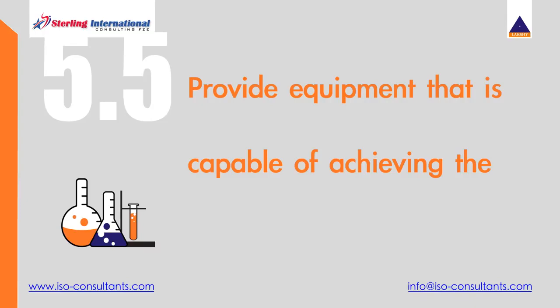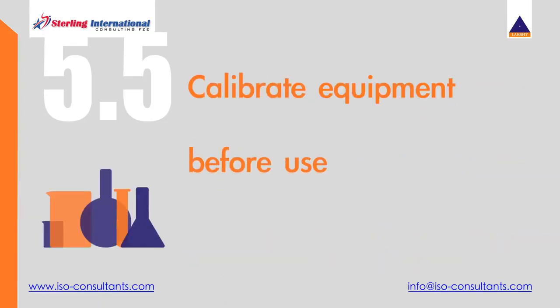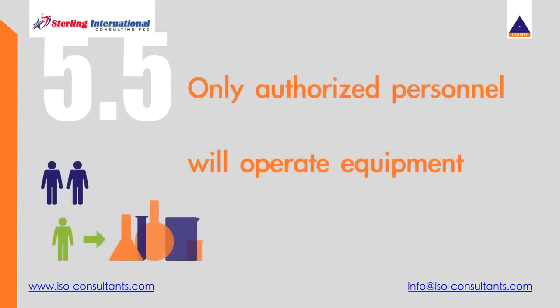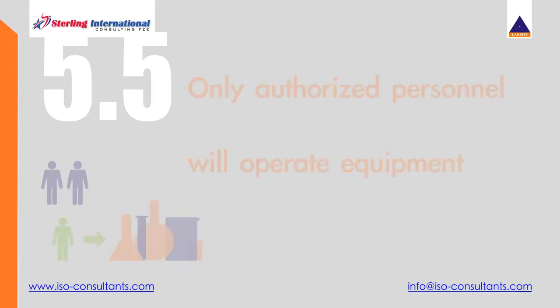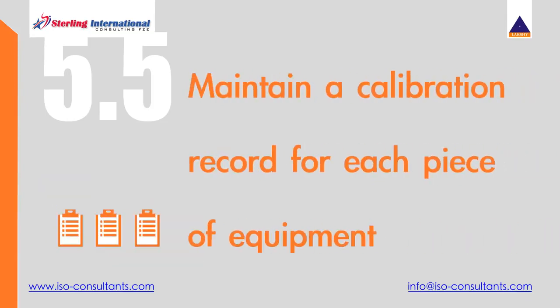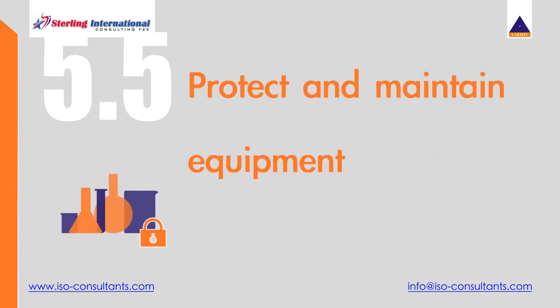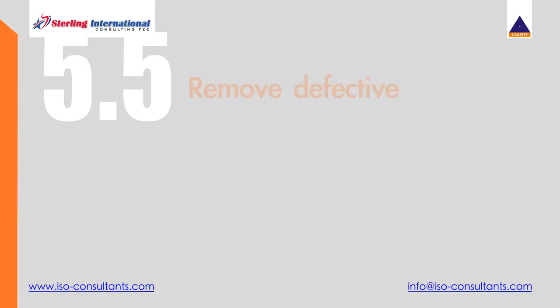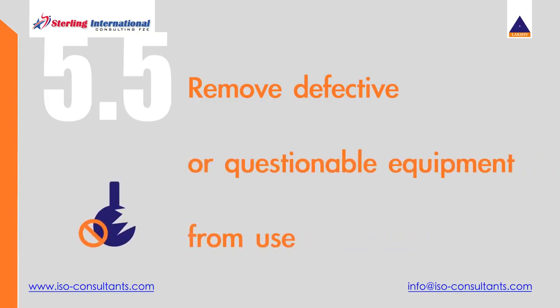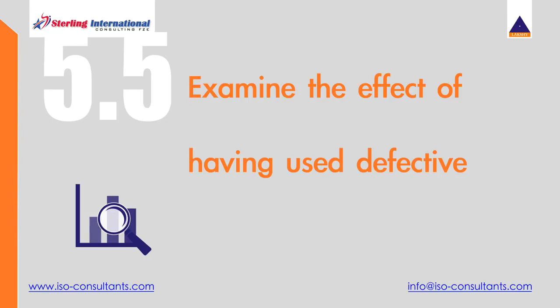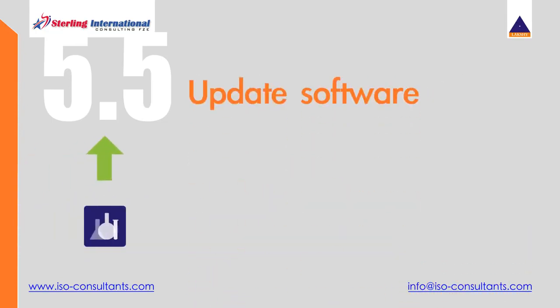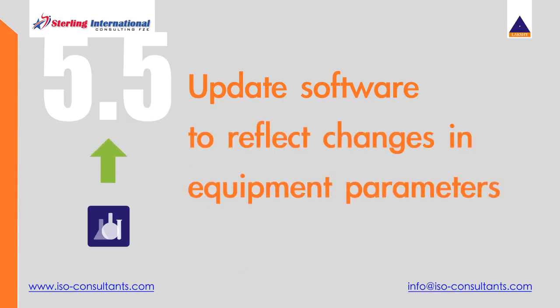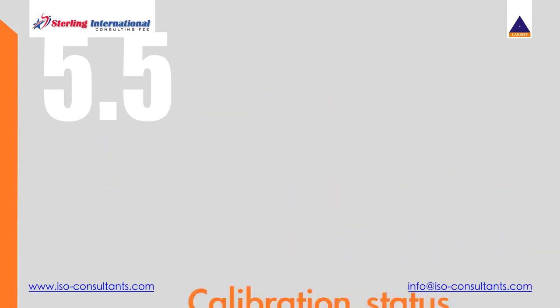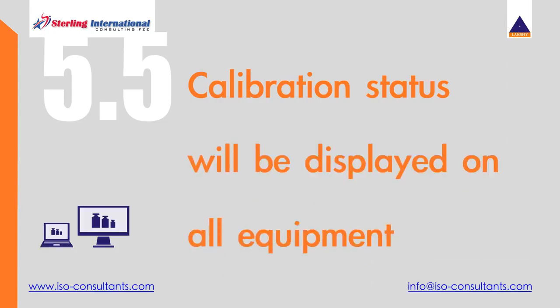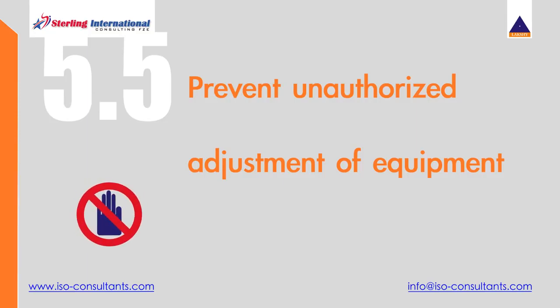5.5 Equipment. Provide equipment that is capable of achieving the required accuracy. Calibrate equipment before use. Only authorized personnel will operate equipment. Maintain a calibration record for each piece of equipment. Protect and maintain equipment. Remove defective or questionable equipment from use. Examine the effect of having used defective or questionable equipment. Update software to reflect changes in equipment parameters or correction factors. Calibration status will be displayed on all equipment. Prevent unauthorized adjustment of equipment.